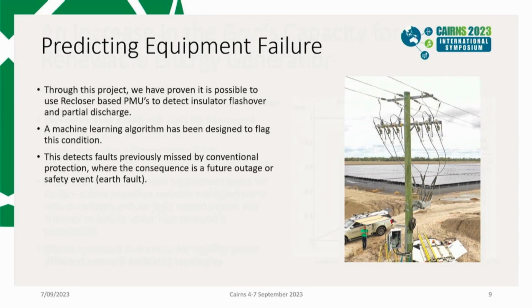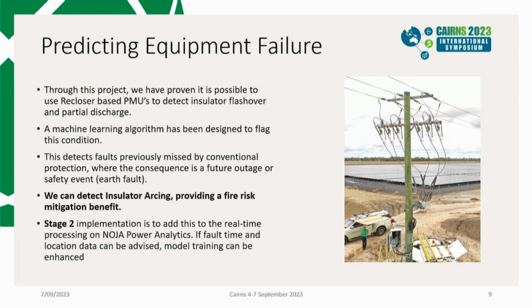More specifically, the PMUs were capable of detecting insulator flashover and partial discharge around the network. Now, this will further require implementation in a real-time system, but a machine learning algorithm was designed to flag this condition based on learning from the data that was gathered. And so it detects faults previously missed by conventional protection, and it also provides the ability to do preventative maintenance rather than relying on a future outage to indicate there being a fault. And so stage 2 implementation was to add this to an analytic system, and some of our utility partners have progressed that implementation over time, still relying on the data that is gathered from these RC20 devices.